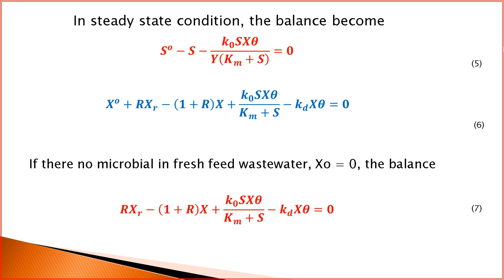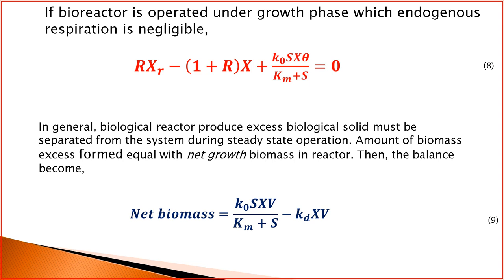If it is assumed that there are no microbes in the wastewater feed (X0 = 0), the balance becomes: r·Xr − (1 + r)·X + k0·S·X·theta / (Km + S) − kd·X·theta = 0. If the reactor operates in the microbial growth phase, endogenous respiration is neglected (kd = 0), so the biomass balance simplifies to: r·Xr − (1 + r)·X + k0·S·X·theta / (Km + S) = 0.